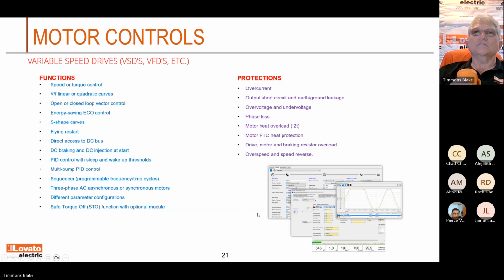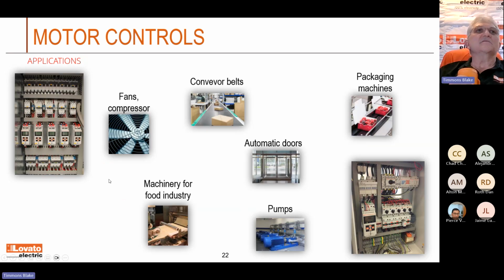just variable speed. Okay. And you can see in a drive, you just have all these different functions and ways to program it, do all this control with it. And then you have a lot more protection out of it. Soft starter, yeah, I can get some single phase detection out of it. I can get some overcurrent detection out of it, but all these braking and resistor overload, overspeed, you just get so much more out of a drive. And the software that comes with the drive, so you usually got a lot more analysis with it. There are some typical applications where you'll see them side by side in a panel for the fans and the conveyor belts and stuff, pumps.